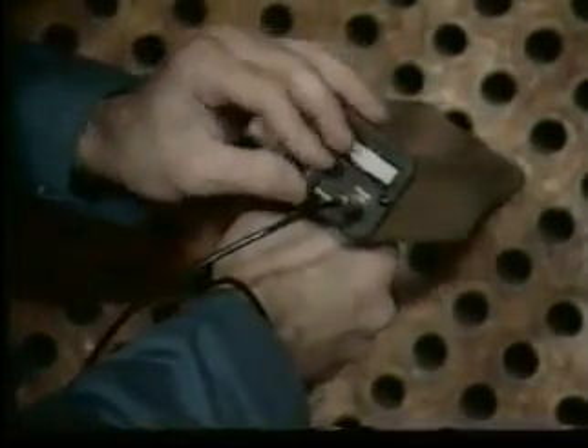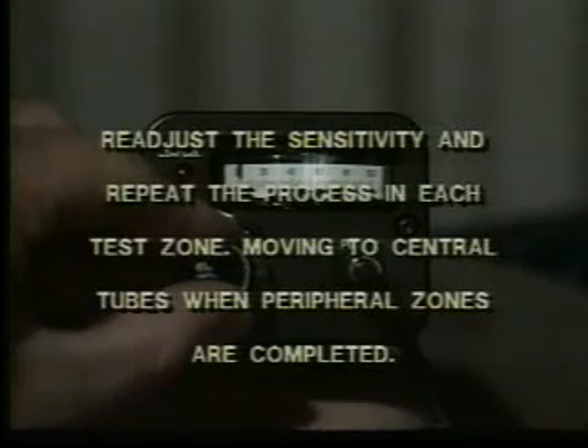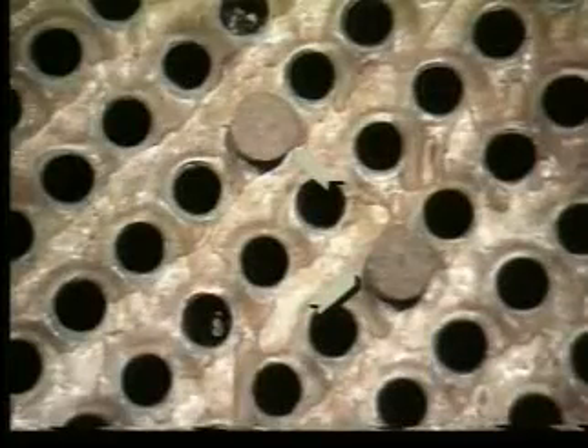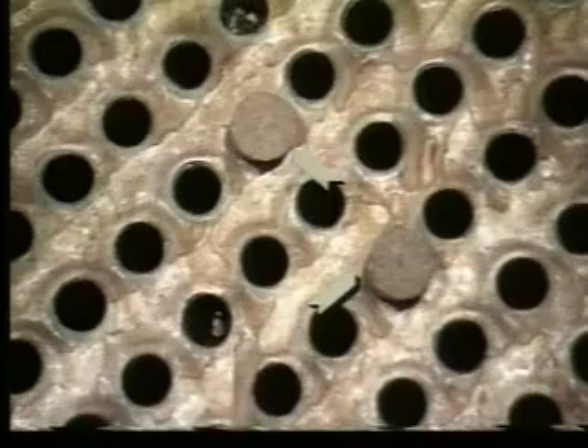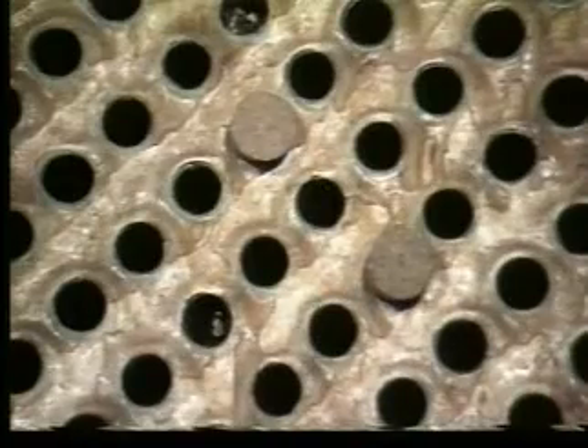To intensify the sound of air in leakage on the inlet side, seal off the outlet tube with plastic wrap. When the loudest area is found, scan around in a star pattern to ensure it is louder and of a different sound quality than the surrounding areas. Mark the loud tubes with cork plugs. A natural progression from one zone to another will be noted by a change in the meter reading. Readjust the sensitivity and repeat this process in each of the test zones, moving to central tubes when peripheral zones are completed. At the end of the test, you will see a visual pattern of corks which may help you determine areas of future investigation for eddy current testing.